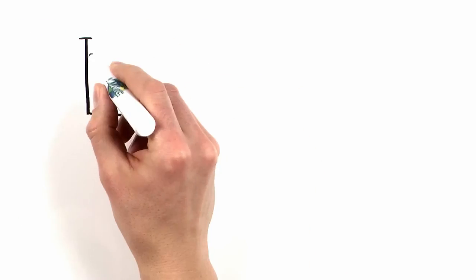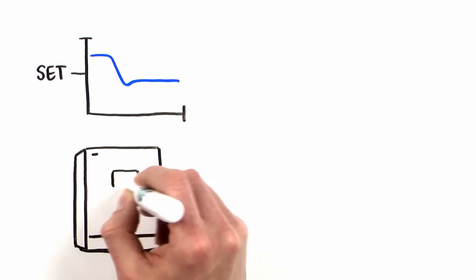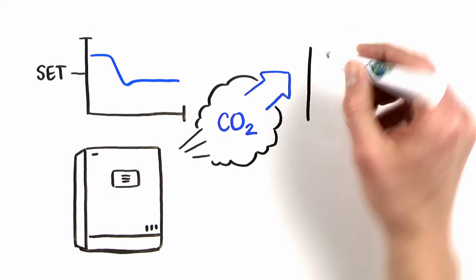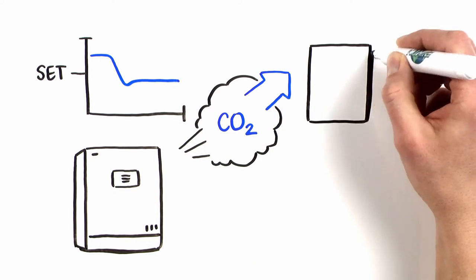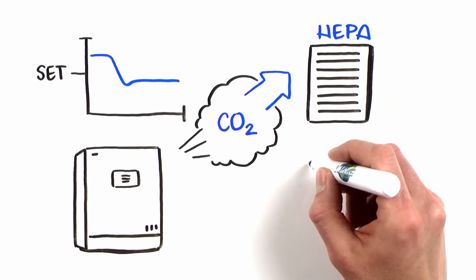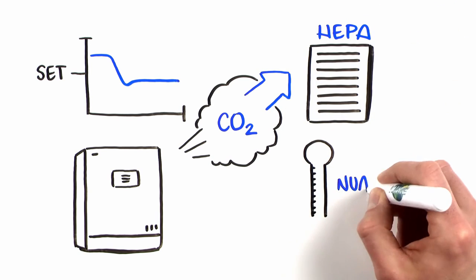When readings are below setpoint, the system injects CO2. The gas or air passes through 99.99% efficient HEPA filters before entering the chamber.